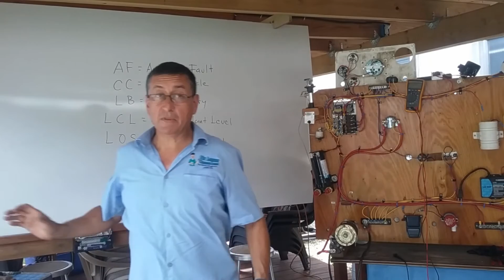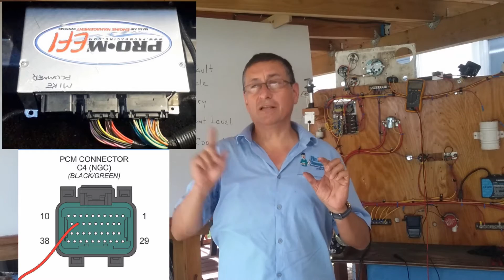If the diesel engine of the generator has electronic fuel injection, you need to verify in the computer what pin you have on the screen right now. You need to check in the manual which pin is for the fuel injection solenoid of the fuel injection pump. It's pin 17, and you check pin 17 with the voltmeter to verify if voltage is coming out. Normally the voltage is around 4.7 to 5 volts. This is another procedure you'll find in our marine diesel engines book.